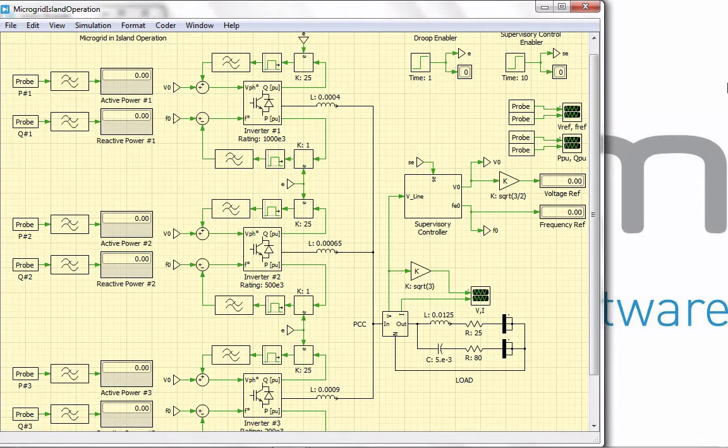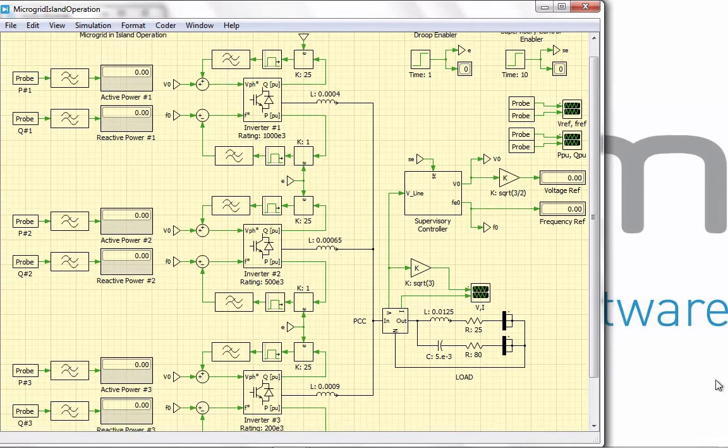The active generators here are modeled using averaged inverter blocks because inverters can provide the control and flexibility required for a microgrid operation. The three inverters have three different volt ampere ratings of 1 MVA, 500 KVA, and 200 KVA. The average configuration of the inverters is modeled using a masked subsystem.